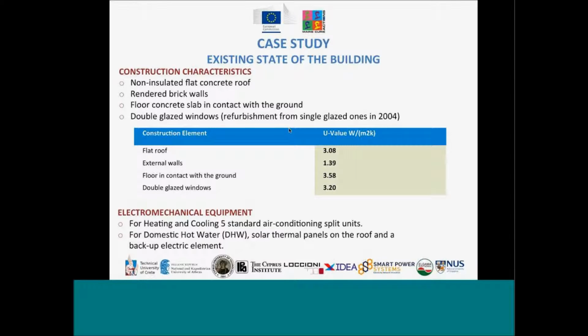So, the characteristics of this building which affect the energy consumption are that it has a non-insulated flat concrete roof. It has rendered brick walls, a floor concrete slab in contact with the ground, and double glazed windows, which have been refurbished in 2004. The electromechanical equipment consists of 5 standard air conditioning split units for heating and cooling. And for domestic hot water, we have solar thermal panels on the roof, which is the normal case for Cyprus, since about 95% of the buildings have these solar thermal panels and a backup electric system.